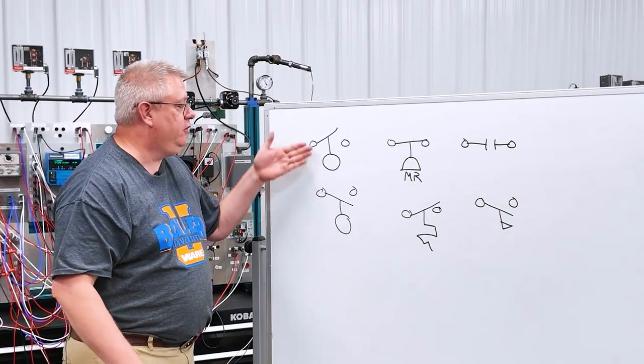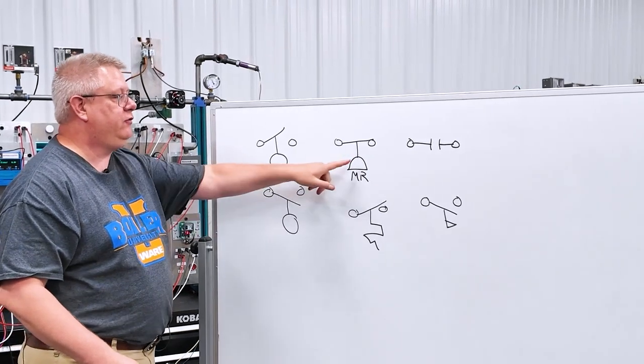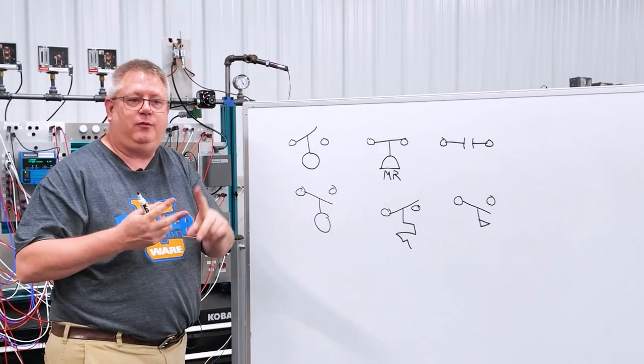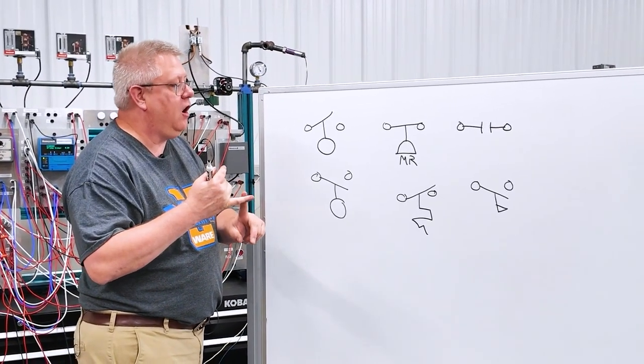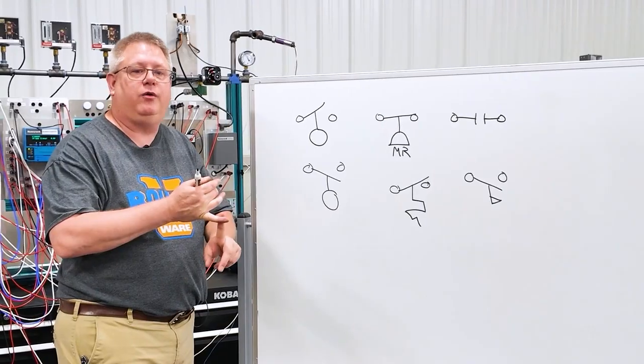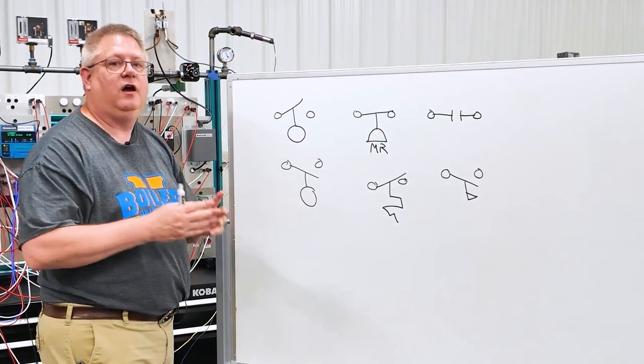Floats, by and large, are used exclusively for level alarms. Pressure switches could be that combustion air. It could be high steam pressure, high high steam pressure. It also could be low oil pressure, if we've got a low or high oil pressure switch on a boiler. So we'll see recurring instances of that.